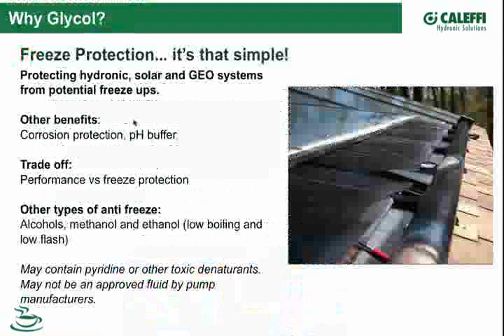So pressure is critical to keep the fluid from boiling. You need to pressurize the system about 5 pounds per square inch above the expected vapor pressure of the fluid, and we publish the vapor pressure of our fluids in charts in your engineering guide that show all those points.